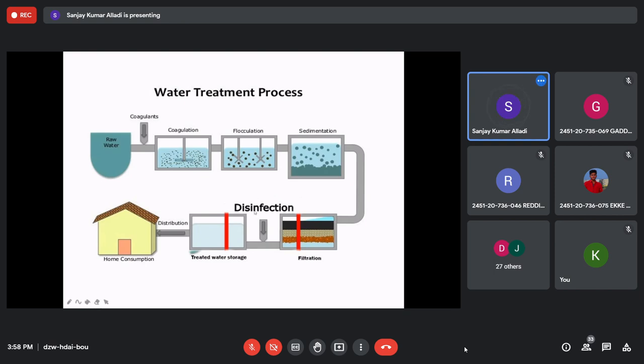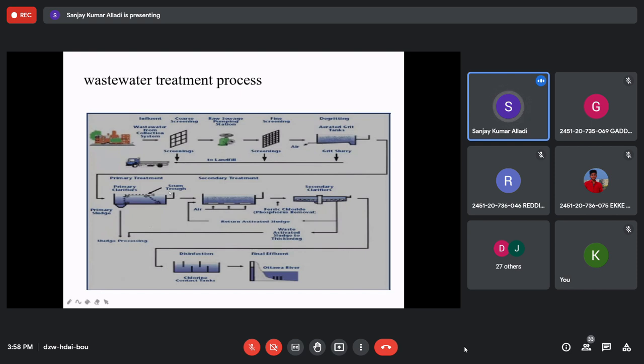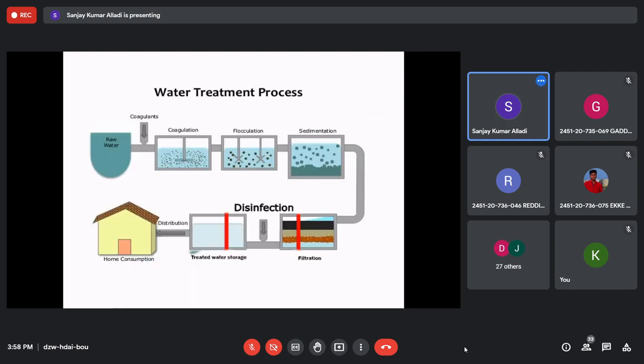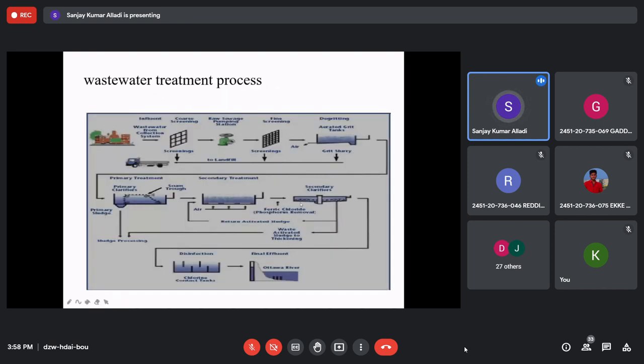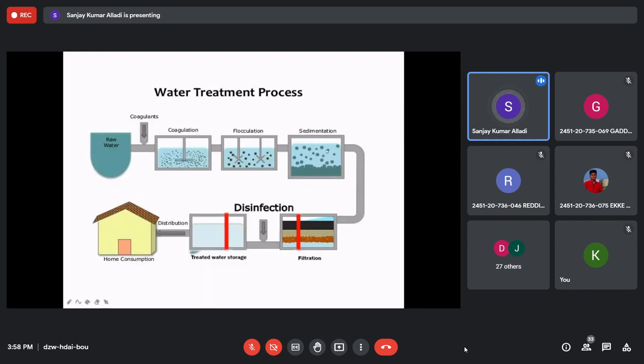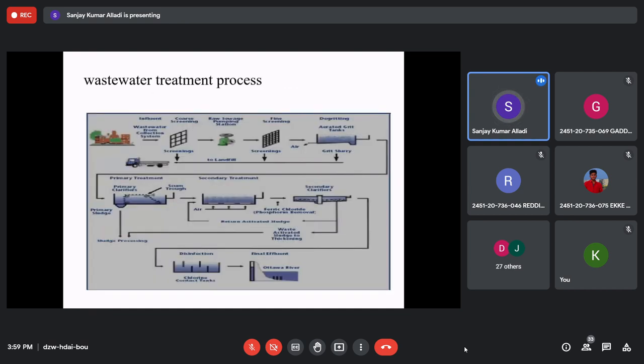This is primary treatment. Next, wastewater from industries or residential houses — sewage water — also passes through the same primary treatment: screening, grit removal, sedimentation, aeration, and then addition of coagulants like alum (aluminum sulfate, Al₂(SO₄)₃·18H₂O), ferric sulfate, or ferric chloride. A secondary clarifier tank is used after aeration and coagulant mixing.